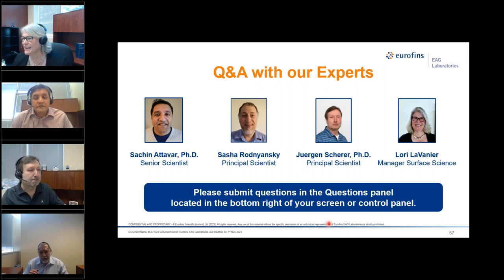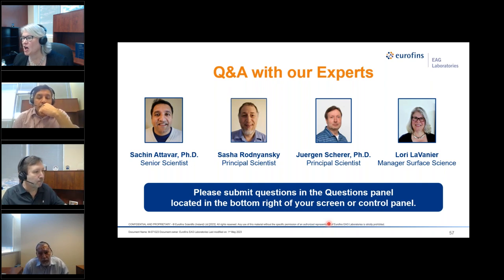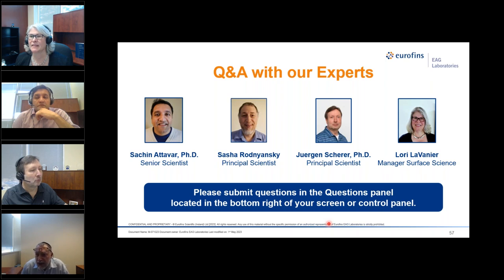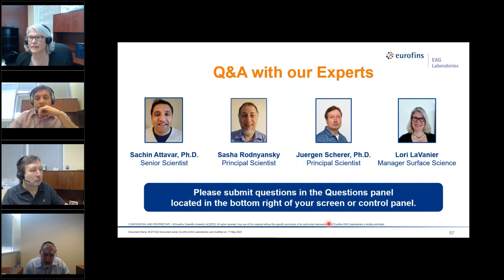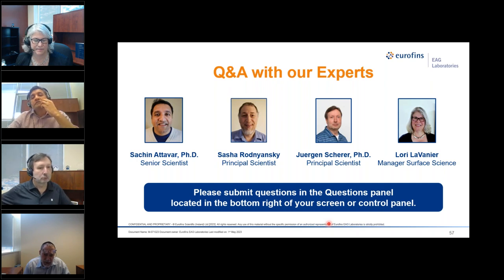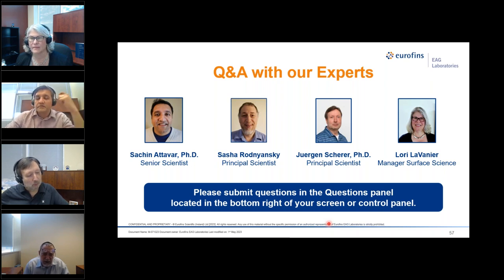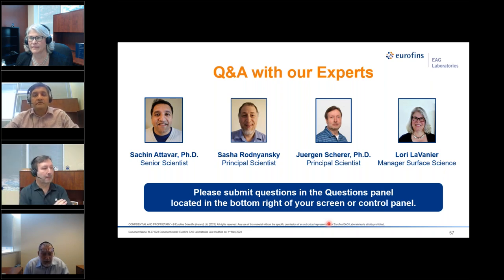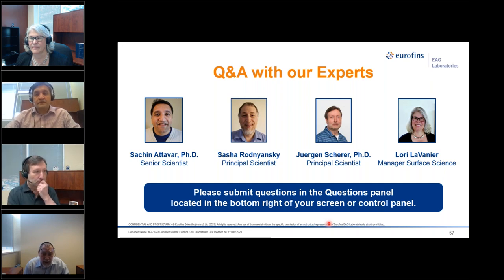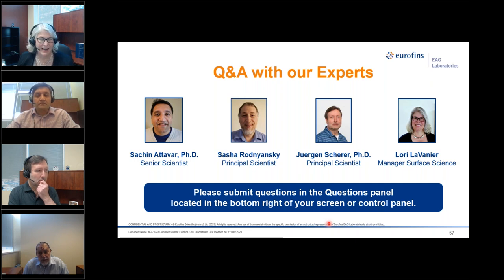An XPS question for Sasha: is depth profiling available on all XPS machines or just a feature on some? To the best of my knowledge, most modern XPS instruments have at least a monoatomic argon ion gun, so you can do profiles of inorganic materials. As far as C60 guns or argon cluster guns, some instruments are equipped with them but many are not — you really need to look for a specific instrument if you need to do organic profiles. This is a relatively new capability; we were not able to do organic profiling until maybe 15 or so years ago.